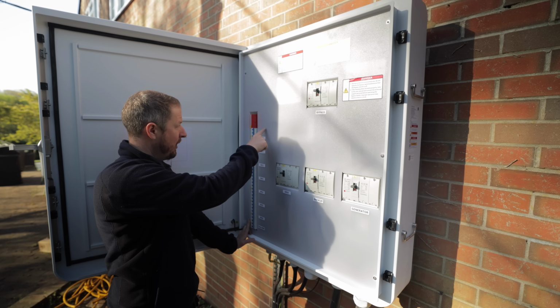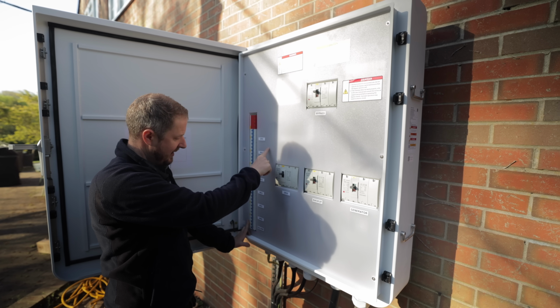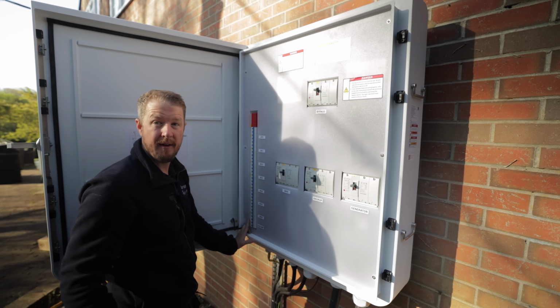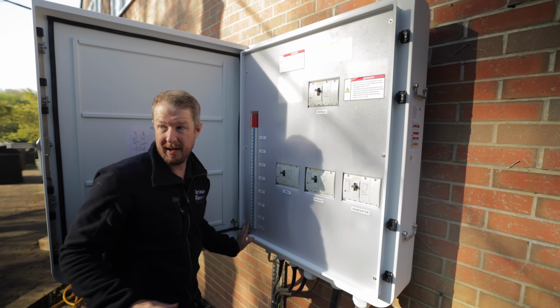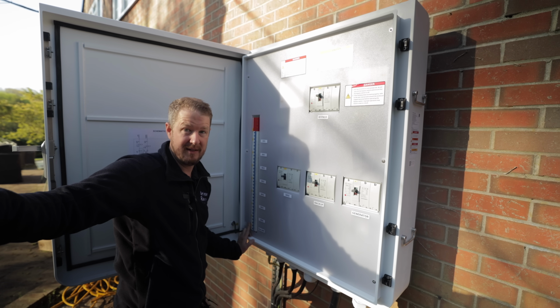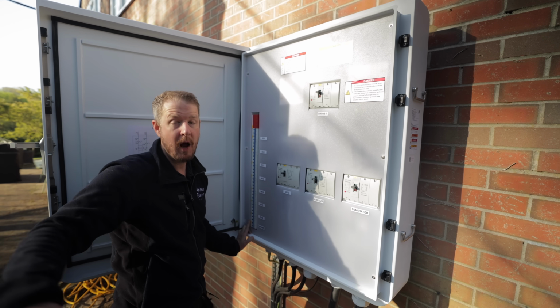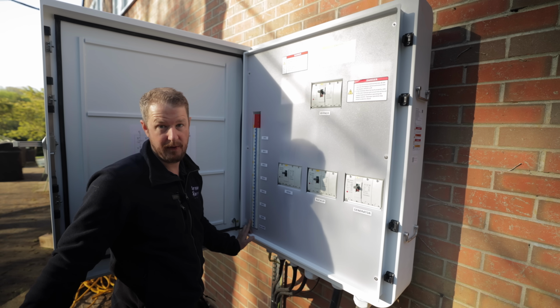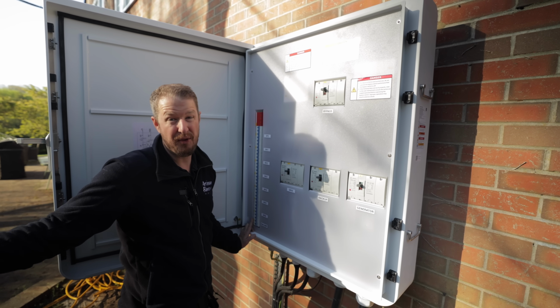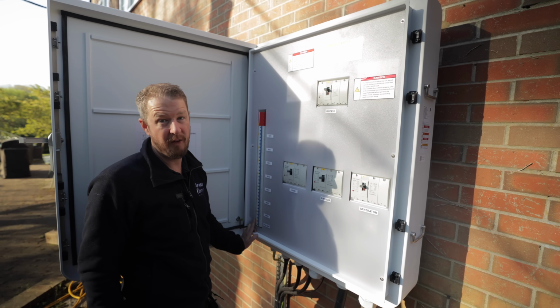Here we've got a surge protection device and 6 outgoing ways for 6 inverters. That means in addition to the 3 inverters and battery stacks we've already fitted, we could fit another 3 in the future if we wanted to, for up to 300 kilowatt hours of battery storage.